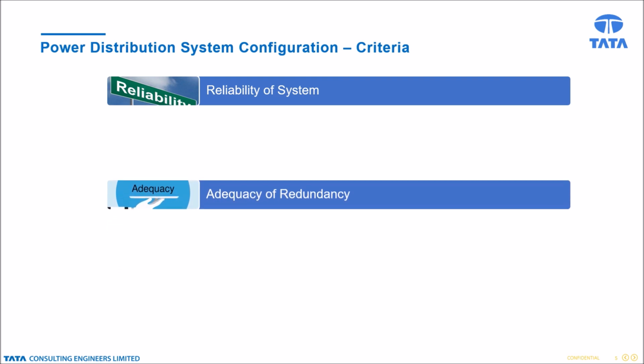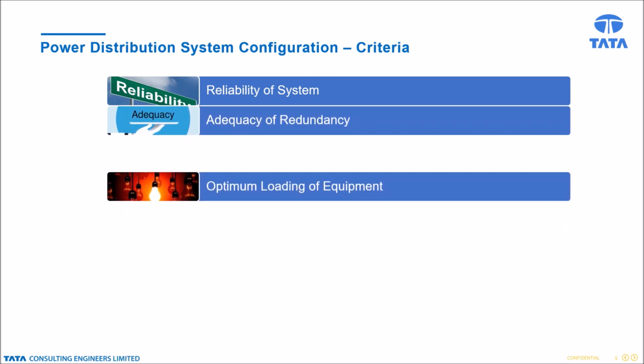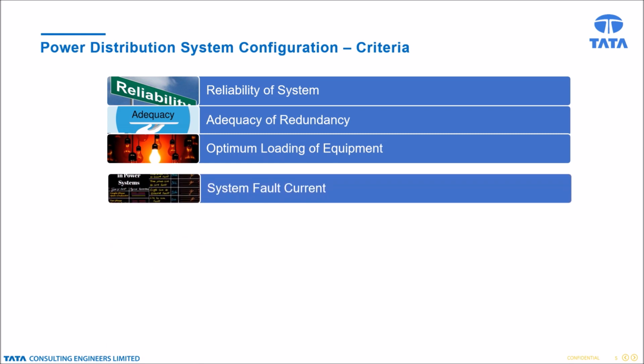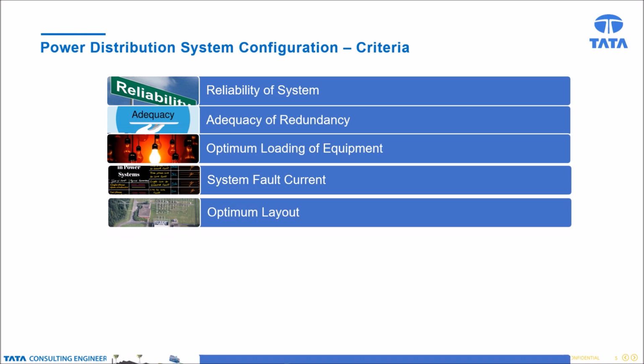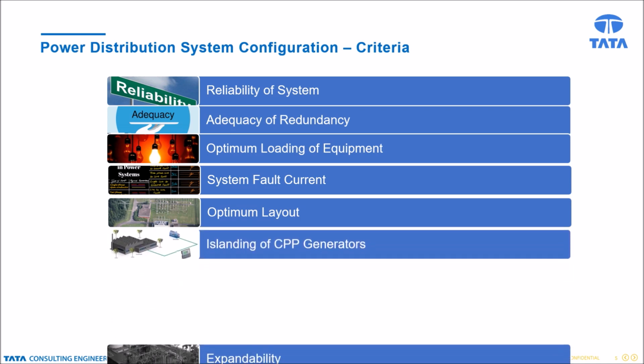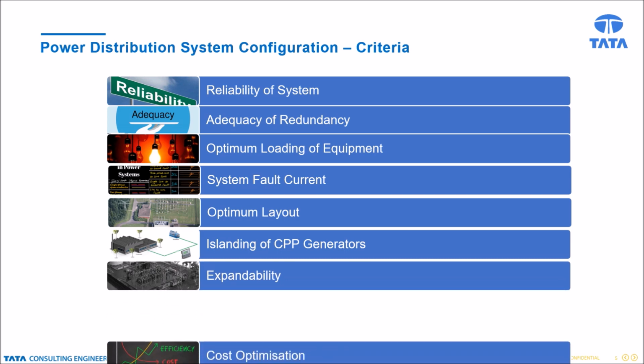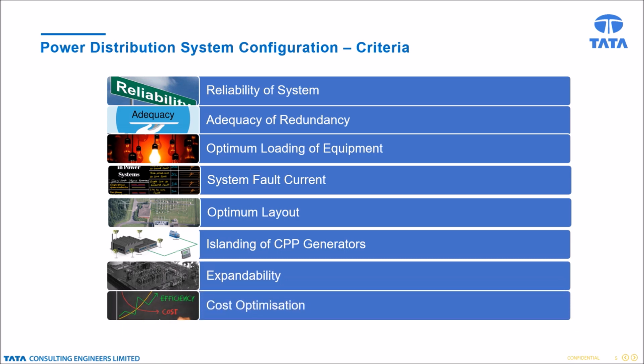The criteria for selection of power distribution configuration is based on reliability, adequacy of redundancy, optimum loading of equipment, system fault current, optimum utilization of layout, reliable and instantaneous islanding operation of captive power plant generators from grid in case of grid disturbances, provision for expansion of power system for allowing future capacity enhancement and cost optimization. System voltage variation should not cause the tripping of critical motors and or drives or of generators due to the operation of under voltage and over voltage relays. Similarly, frequency variation should not trip the generators due to the operation of under frequency and over frequency protections.